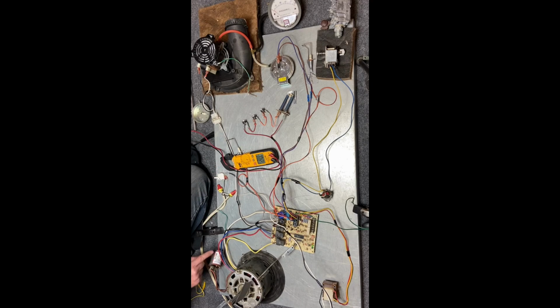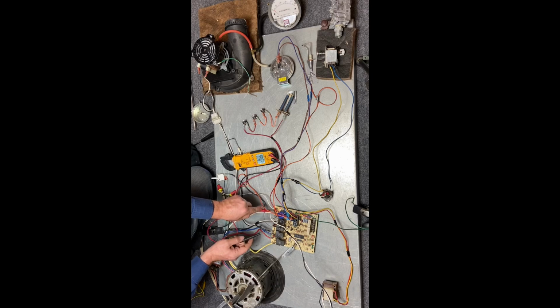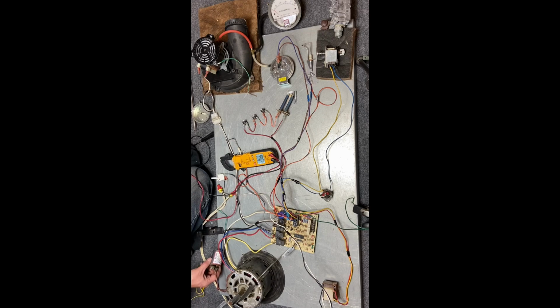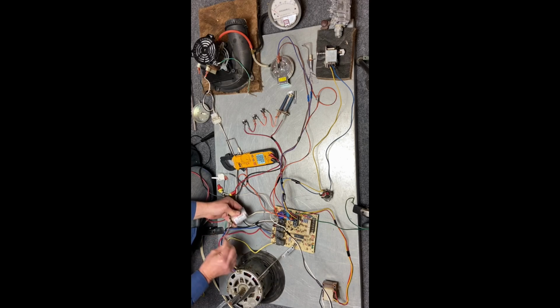Next thing I want to do is talk about this capacitor real quick. So what I'm going to do is disconnect our power, and never assume that it's disconnected. I also want to use my meter and check. I want to check this bottom number for volts between my neutral and my primary, and it's showing 0 volts. So now it's safe to work on. If I look at my capacitor, it's a very common fail part. So what I'm going to do is disconnect these 2 wires of my capacitor. And I'm not going to touch the metal because I don't know if it's holding a charge or not.